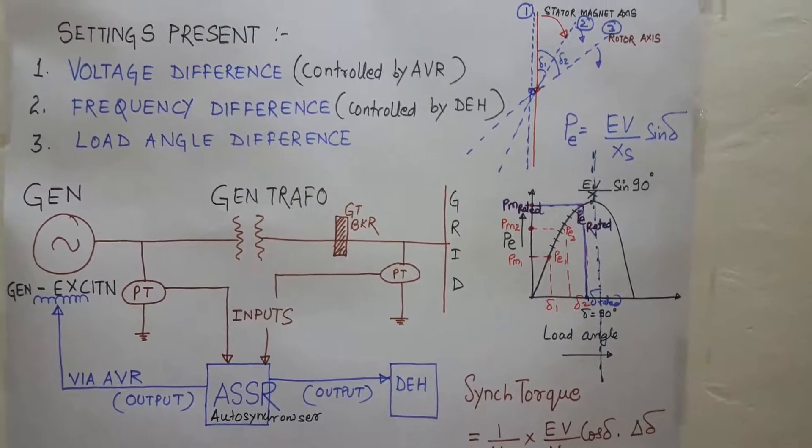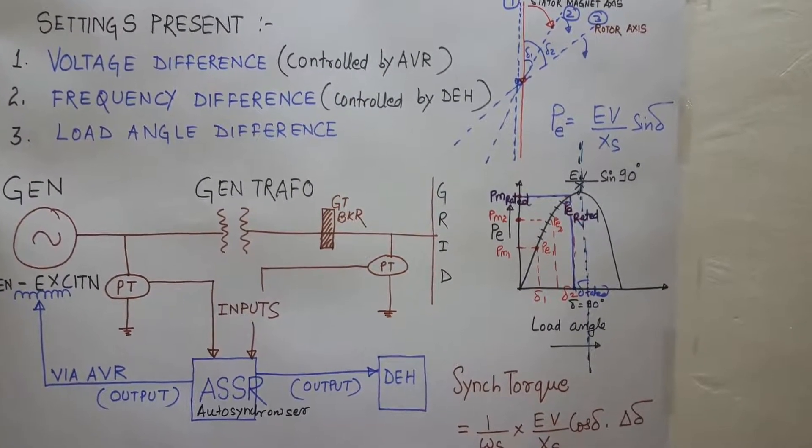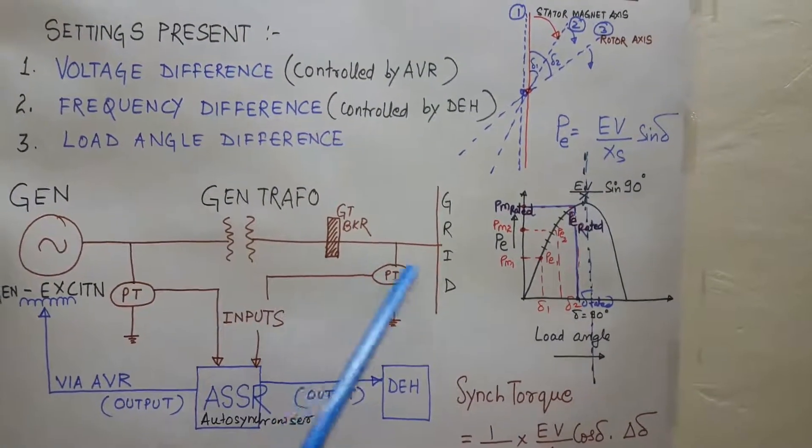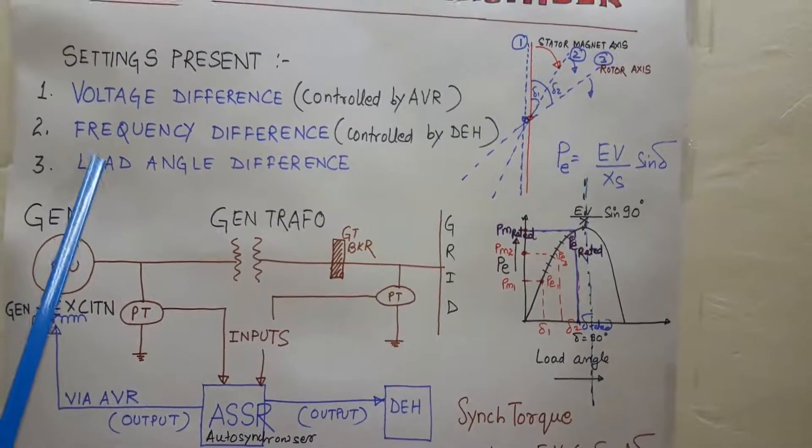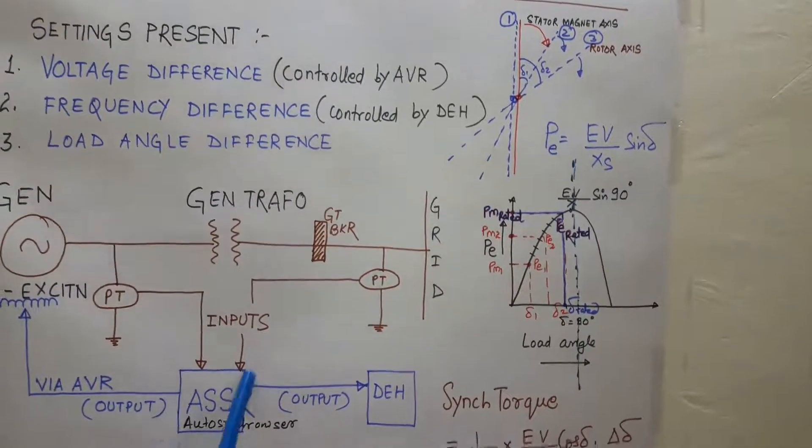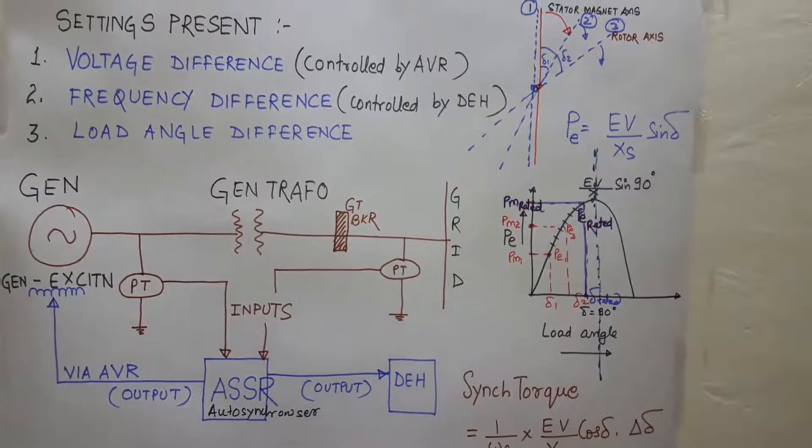By controlling the speed of the rotor, the frequency of the generated voltage can be controlled and can be brought equal with the grid voltage. Similarly, for making the load angle difference within the allowable limit, the auto synchronizer will send a signal to the DEH of the turbine for controlling the speed.